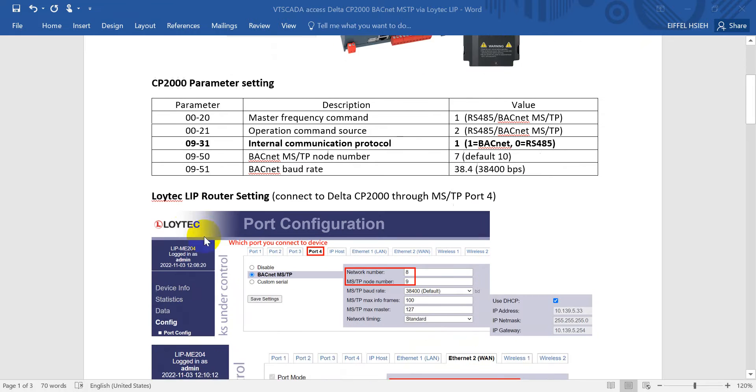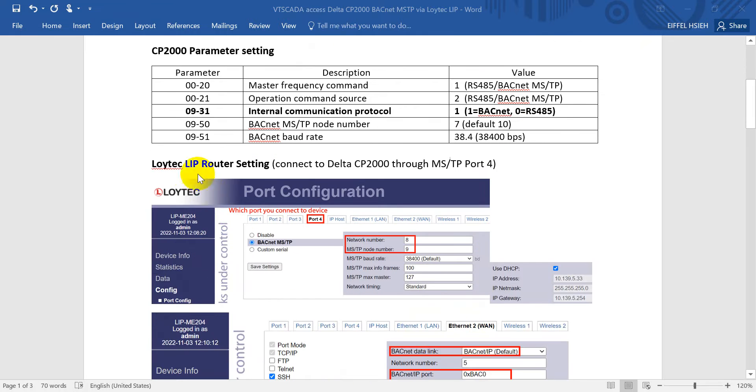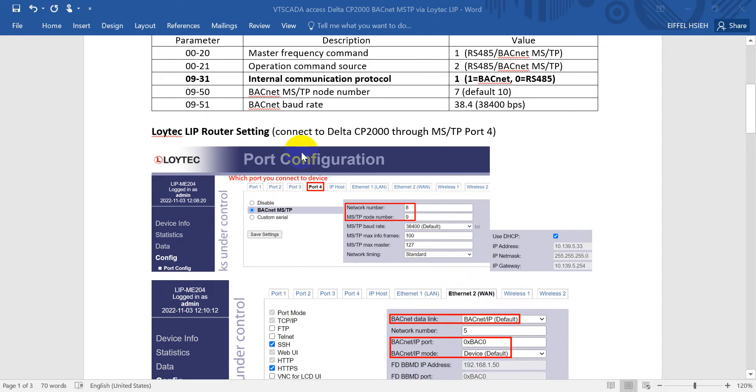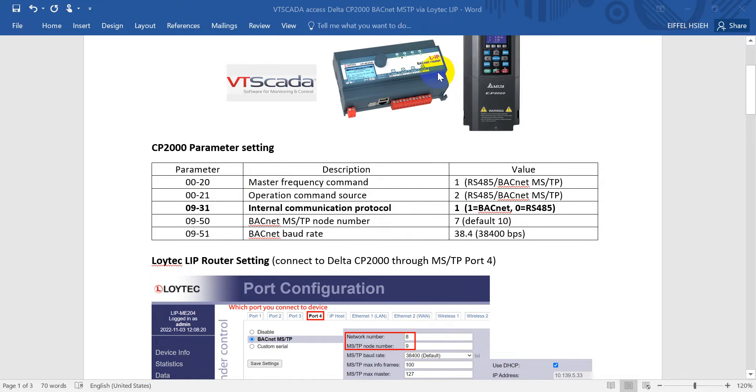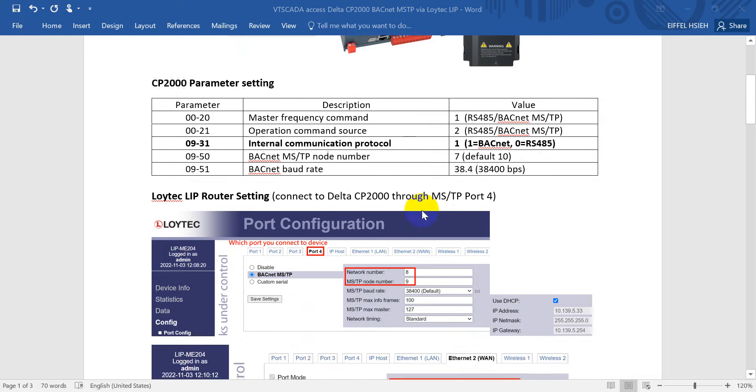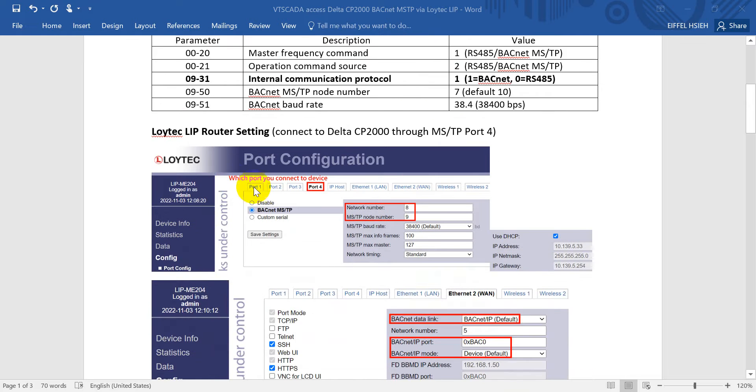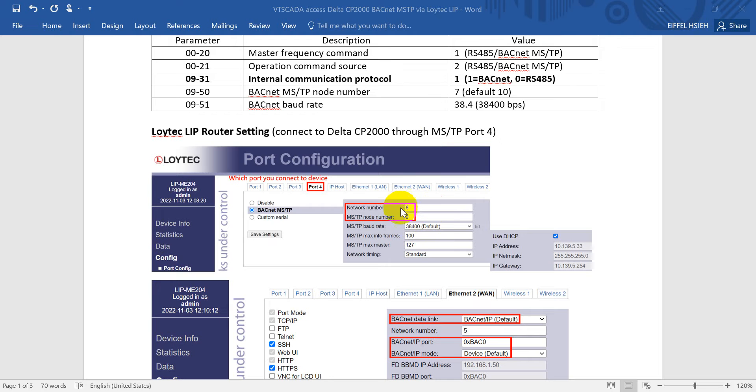Next we'll move to the Loytec LIP router settings. In this example, we will connect to the CP2000 through BACnet MSTP port number 4. Here we have to set up the network numbers for the MSTP node numbers. We will assign network number 8.